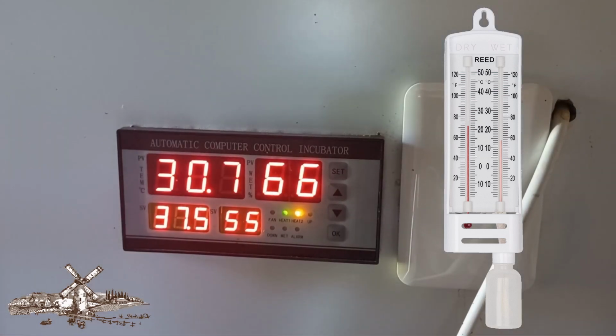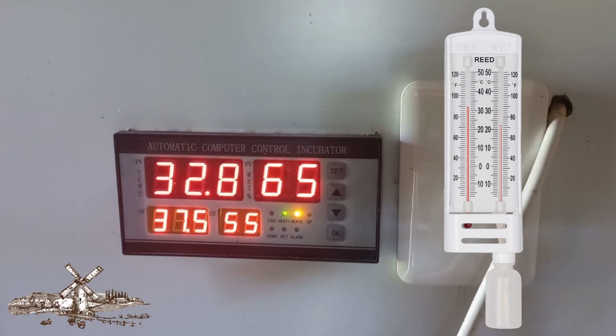Now, unfortunately, I wasn't able to film the wet and dry bulb through the window with enough detail to be able to take a measurement with the camera. And so what I'm going to do for you is animate the wet and dry bulb on the right hand side of your screen so that you can see what the wet and dry bulb was doing inside the machine at that time. Now, my first step is I want to calibrate just the temperature. Right now I'm not going to worry about the humidity. We'll come to that later.